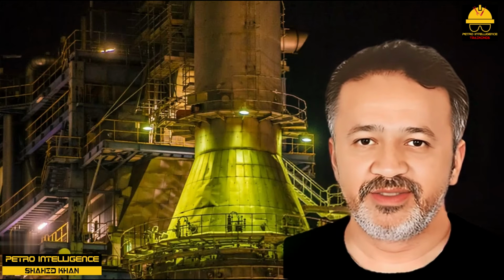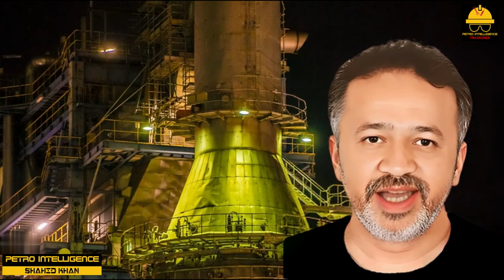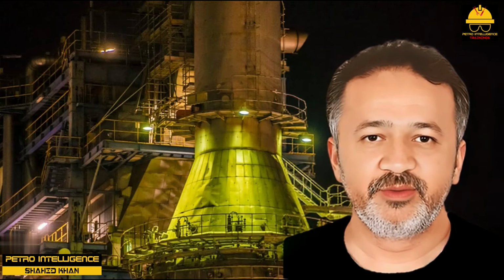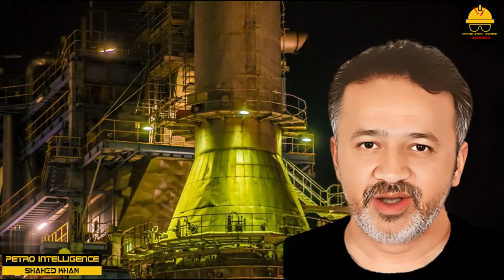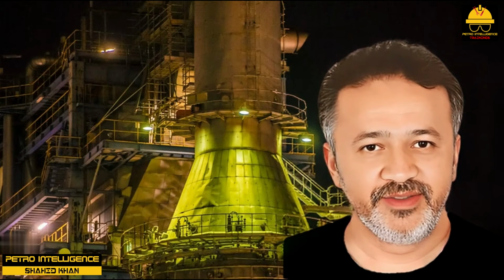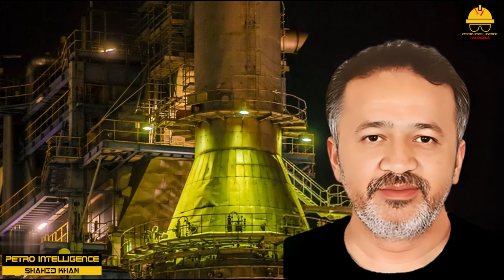Appearance of the firebox and flames. Regardless of and in preference to oxygen analyzer results, we must consider the appearance of the firebox and flames when we assess whether more combustion air is needed. If the firebox appears bright and clear, then there is more than enough oxygen. A crystal clear firebox has a large excess of oxygen.